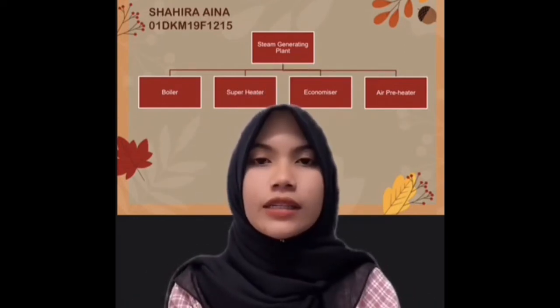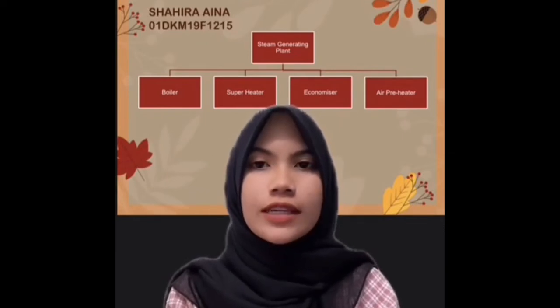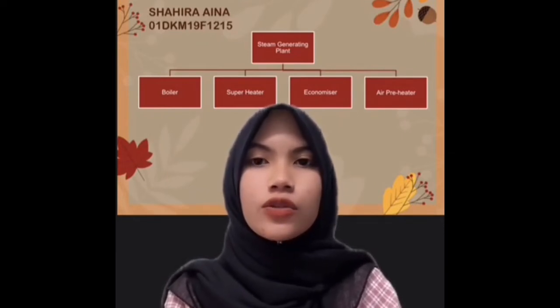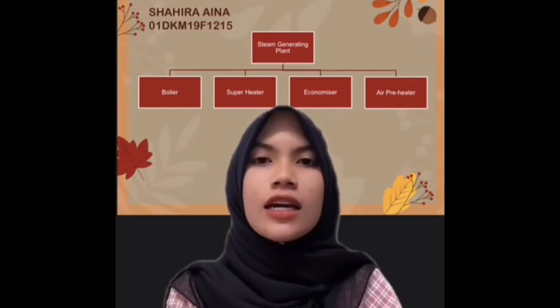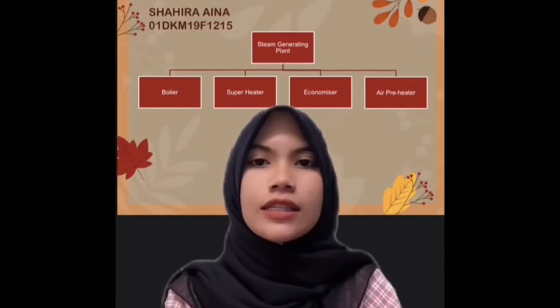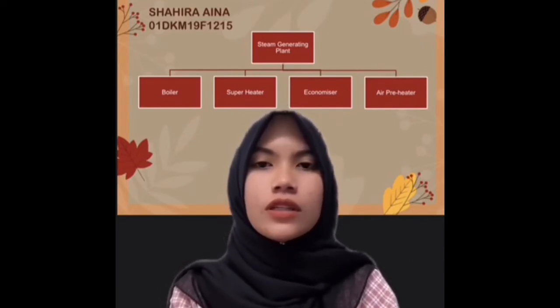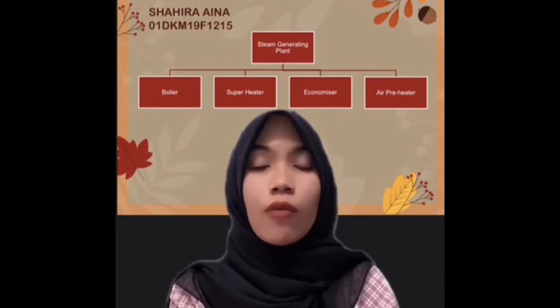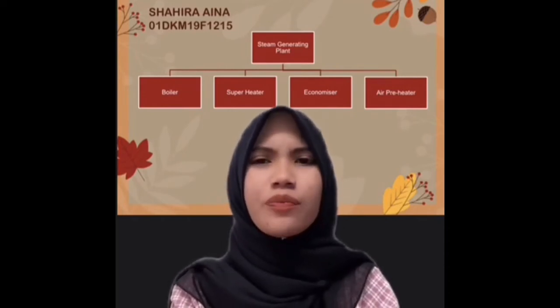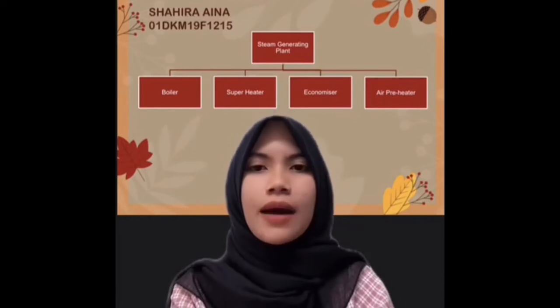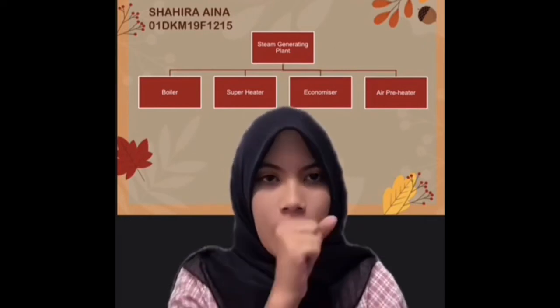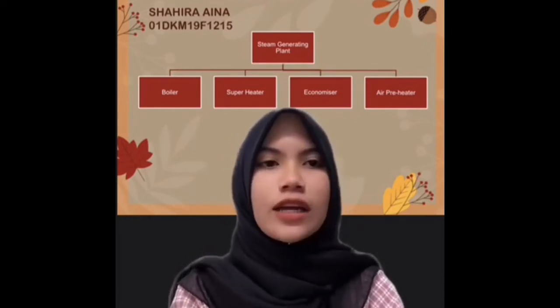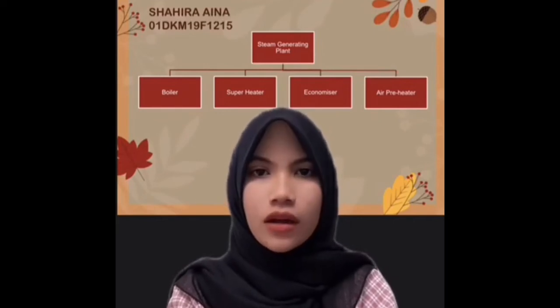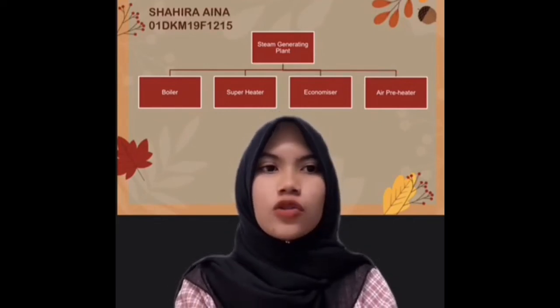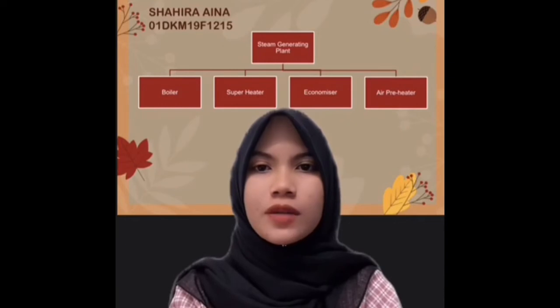Second, superheater. The steam produced in the boiler is heated and is passed through a superheater where it is dry and superheated. The steam temperature is increased above that of the boiling point of water by the flue gas on their way to the chimney. The superheater provides two principal benefits.